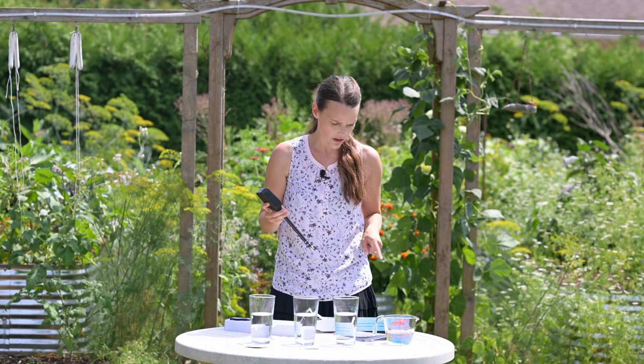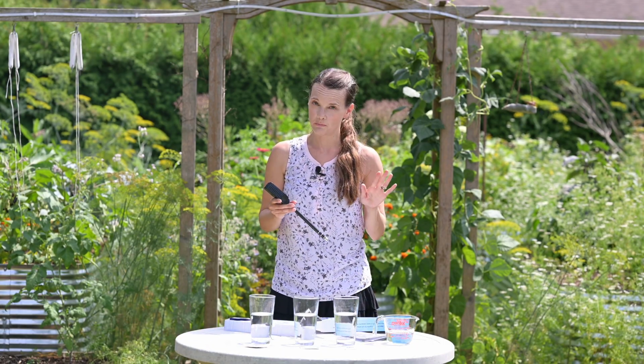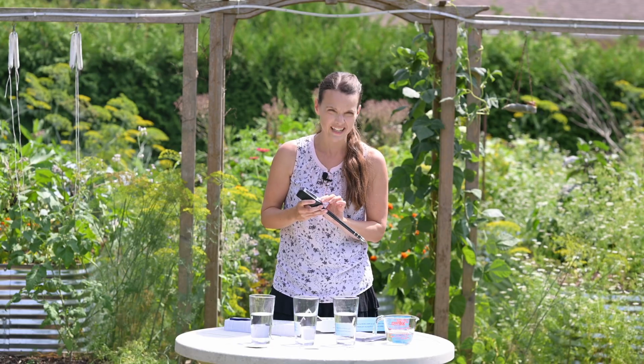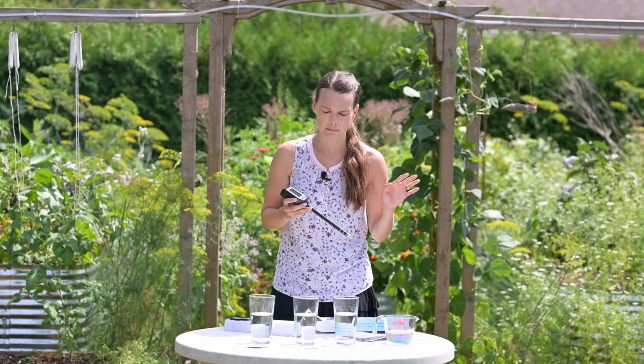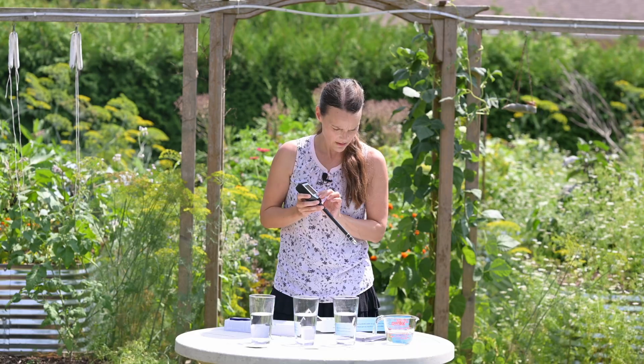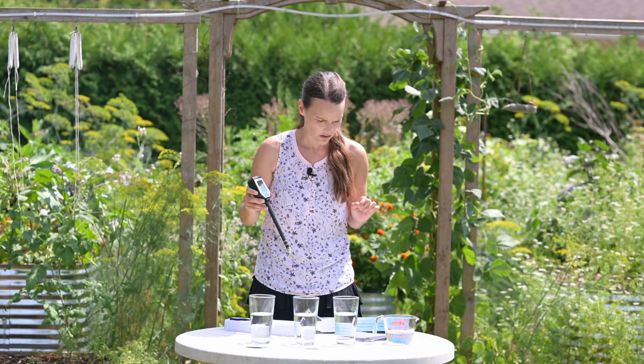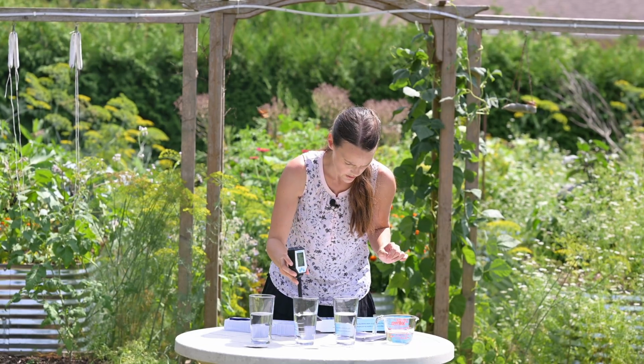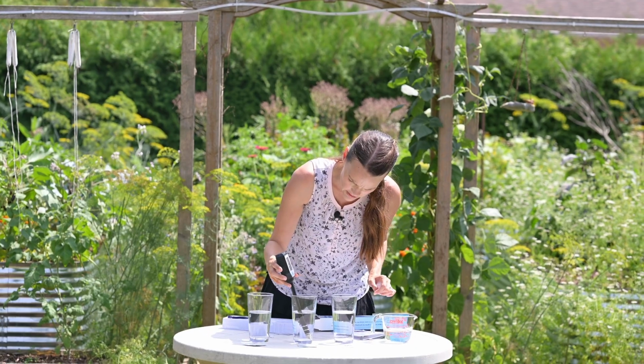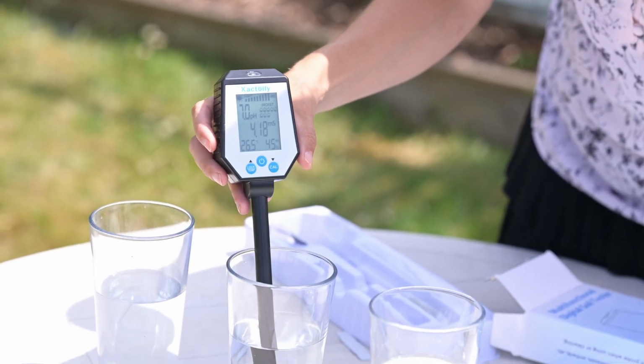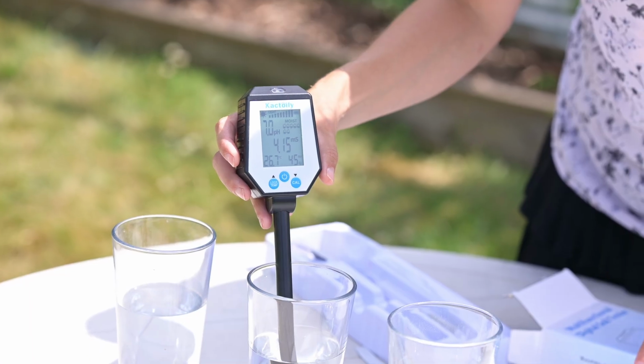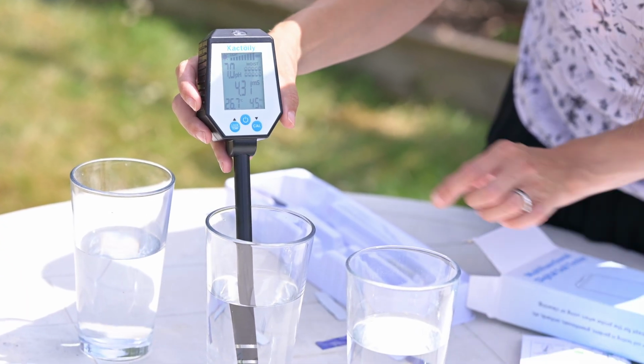Okay, so we're gonna turn it off. So the first thing is power on for the 7.0 calibration. This is like IKEA furniture, and I've got a couple of screws and things left at the end. Okay, turn it on. Put it in the pH 7.0 solution, stir and wait for it to stabilize. 7. Okay, so it's stabilized. Press cal. pH blinking. Press 2 to 3 seconds after pH blinks.